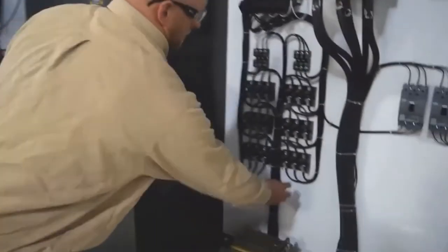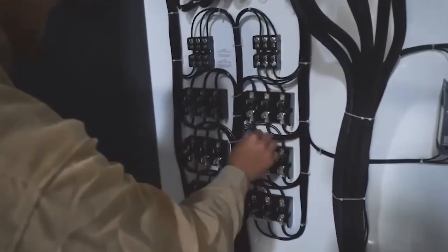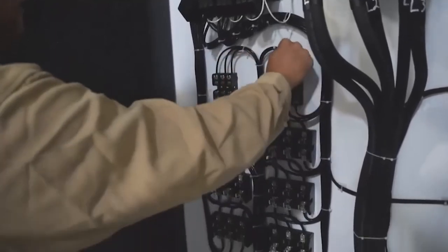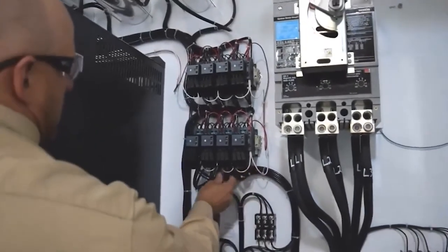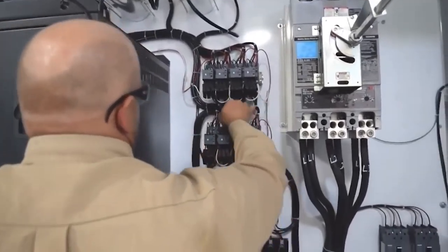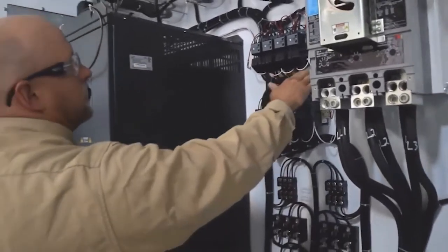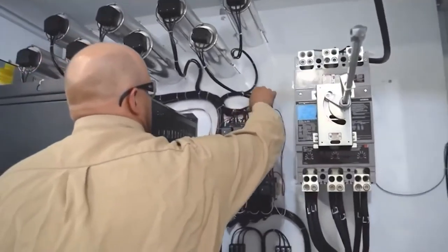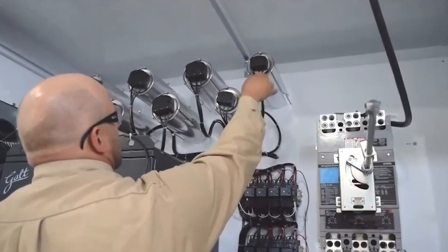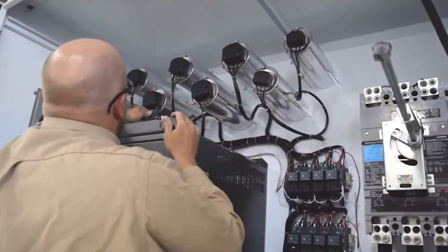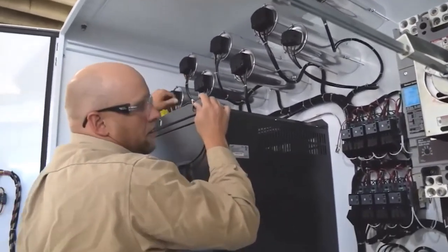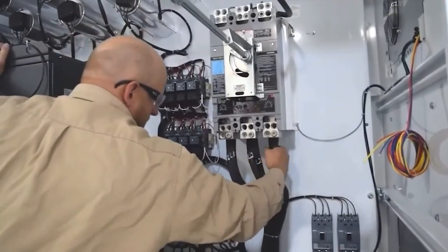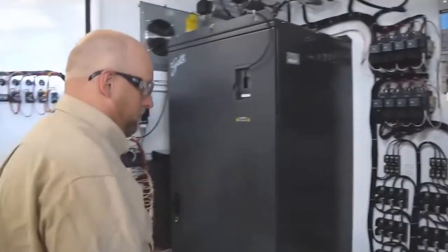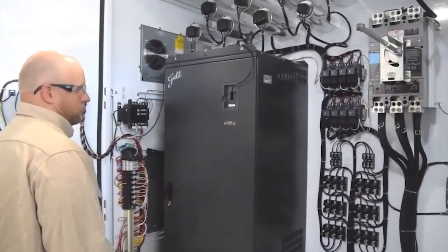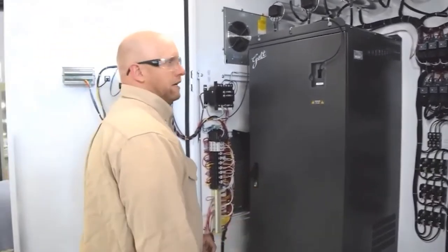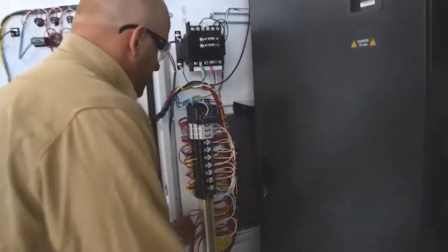In this particular demonstration, we just did a visual pull test. A lot of times when you're checking all the connections, we recommend using an IR camera and doing it while it's energized. Using an IR camera, you can see any hot spots or any loose connections. Another way, if you don't have those available, you could use a torque wrench and verify torque that way. As you're going through these connections, you can give them a pretty good tug, especially on high power connections. If they feel like they move at all, they probably need to be retorqued. So as we move through, like I said, look for anything that's burnt, anything that's crispy, anything that looks to be there that doesn't belong there.